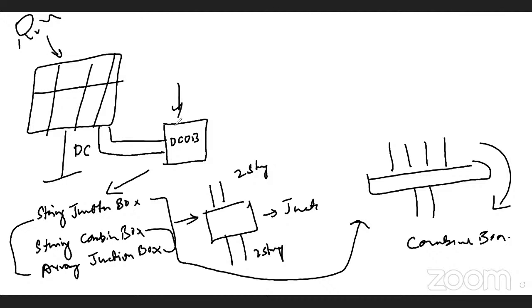So if the capacity of the inverter is more, probably you have to parallel the strings and make them one string and bring it together to connect it to the MPPT of the inverter. In such cases, we will combine more strings into fewer strings by making parallel connections. So these 2 will become one and these 2 will come as one string. So with respect to the DCDB, it can be a junction box or combiner box based on the application, whether you want to combine more strings into fewer or you want to just provide the safety. The main ultimate aim of making any DCDB is to provide the safety.